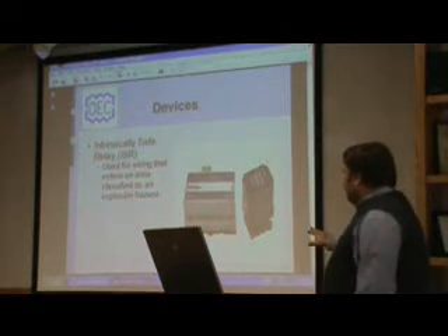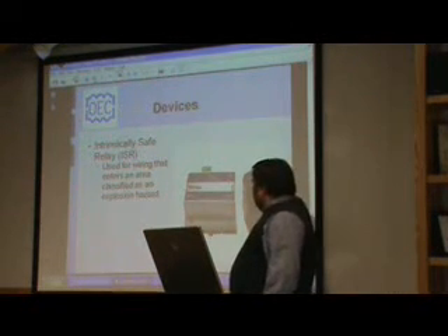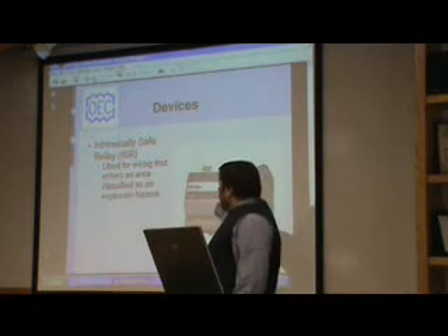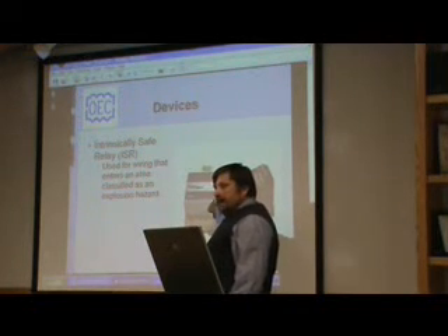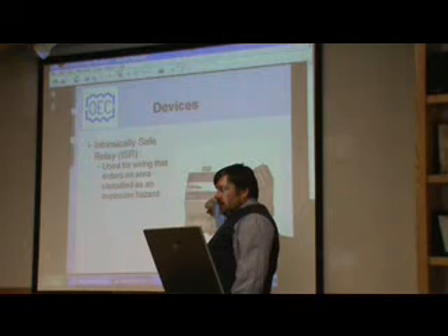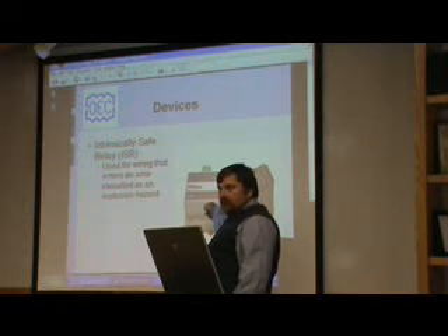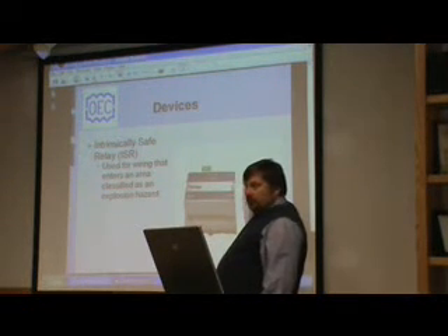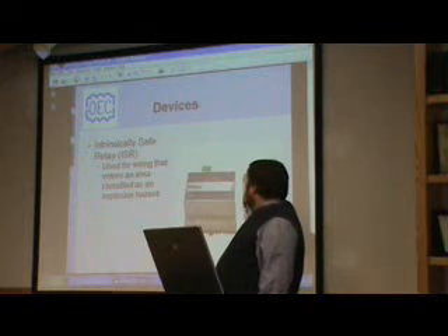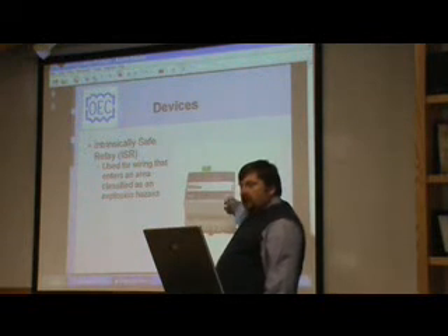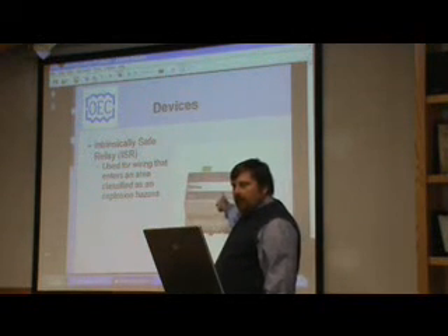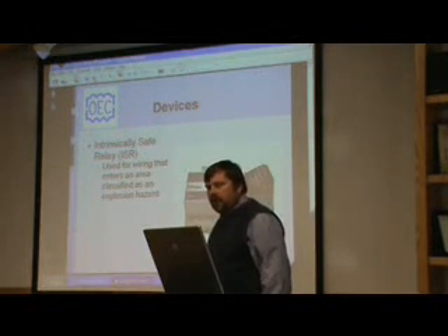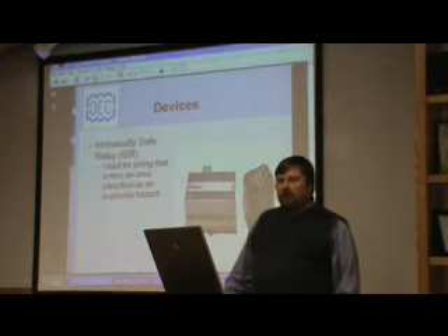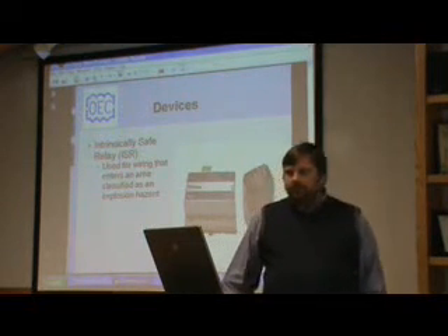Up here you see the couple different devices. We use the single channel device. They also make a 4-channel or 5-channel device. I like the single because if one channel goes out here, you replace this whole device. If one channel goes out here, you only replace one. Plus, if one ISR goes out, you can pull the lag one out and move it over and plug it in where the one was, and your panel's back to working, and you can get another ISR to replace back into the lag position.